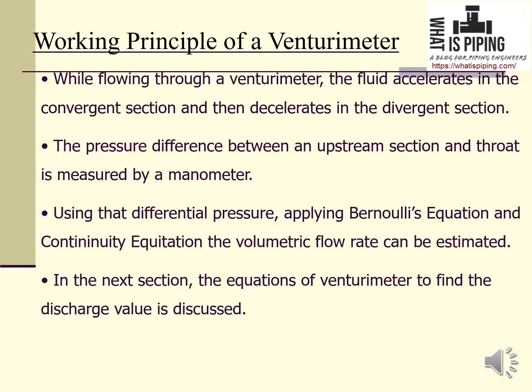The working principle: while flowing through a venturimeter, the fluid accelerates in the convergent section and decelerates in the divergent section, meaning fluid velocity increases in the convergent section and decreases in the divergent section. The pressure difference between the upstream section and the throat is measured by connecting a manometer. Using that differential pressure and applying Bernoulli's equation and the continuity equation, the volumetric flow rate can be estimated.